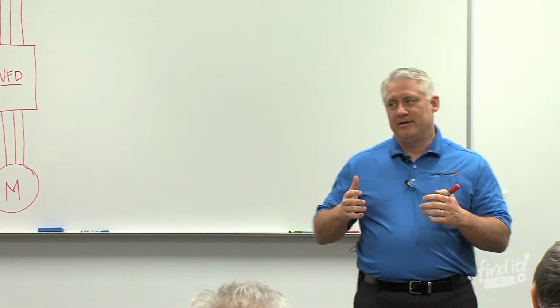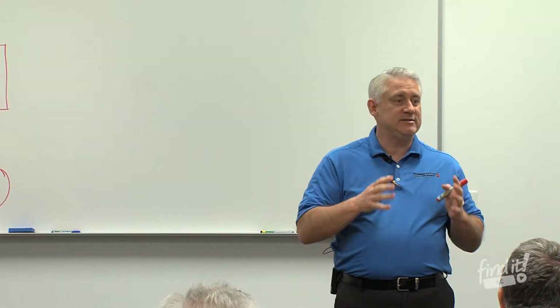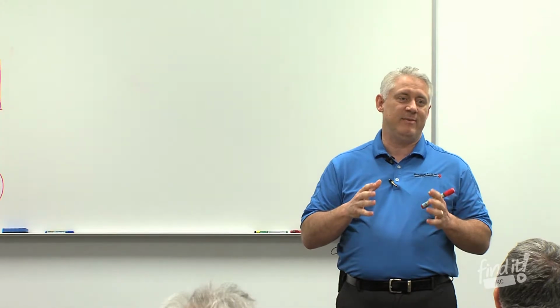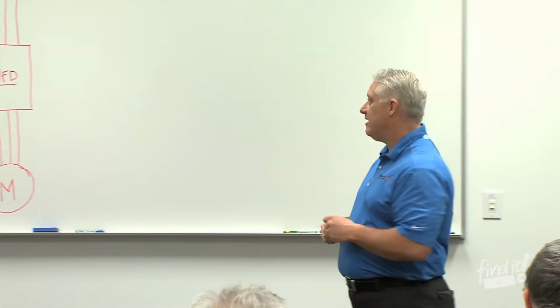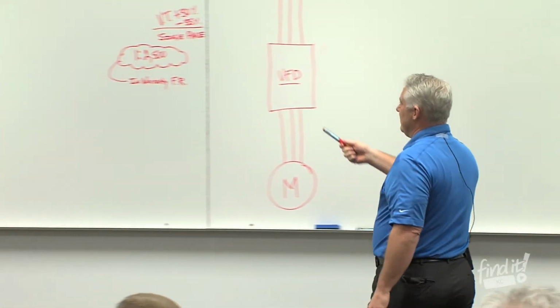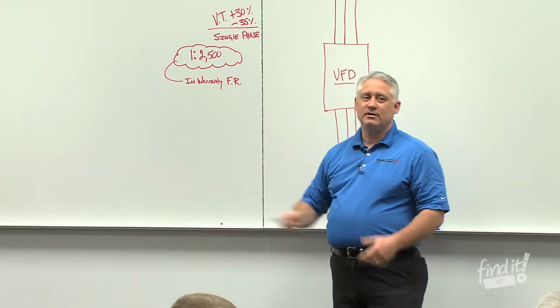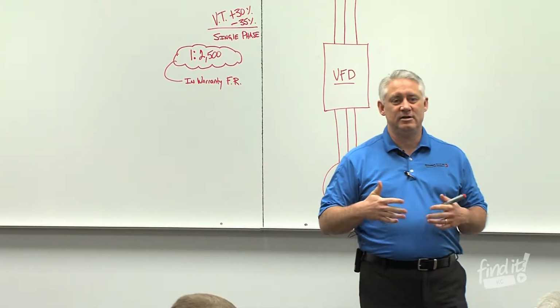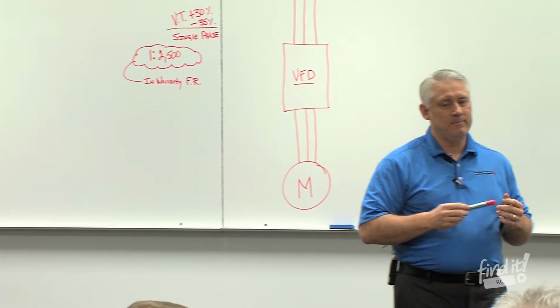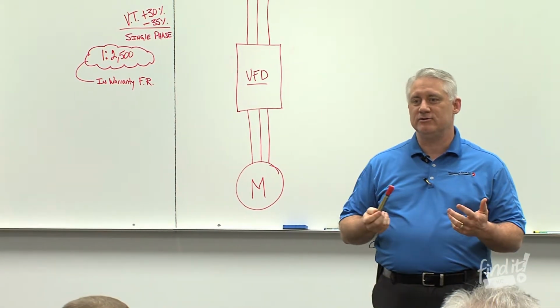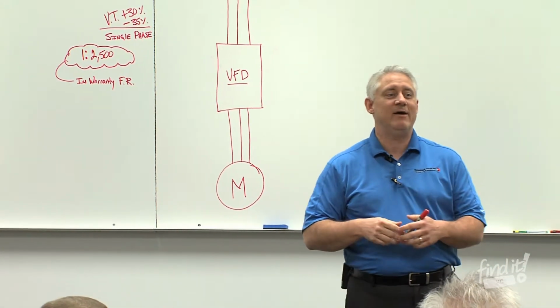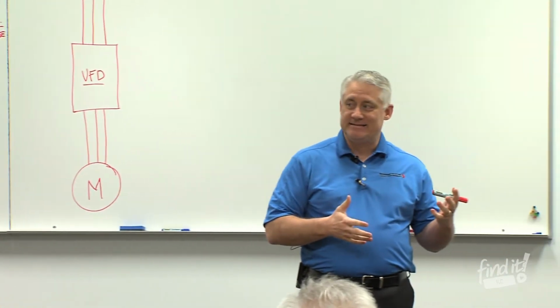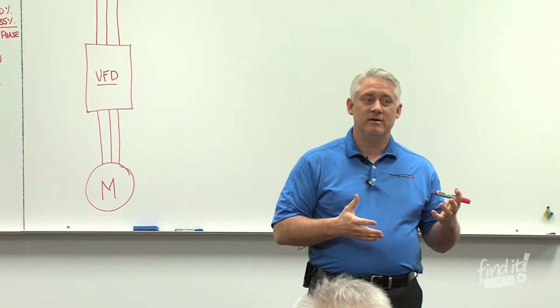So really what I want you to think about today is, today still 80% of the drives we sell have bypasses on them. But with these kinds of failure rates, if you don't have a supercritical application, do you really need to have a bypass? So we're going to talk a little bit about that. Because when we start adding additional control to the drive, we're now making the drive and bypass system as a whole less reliable.